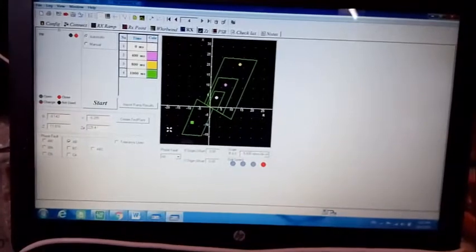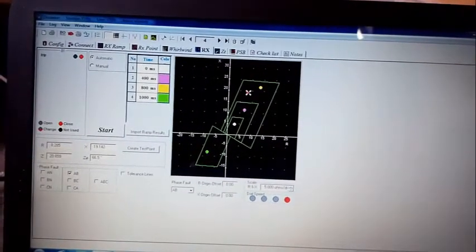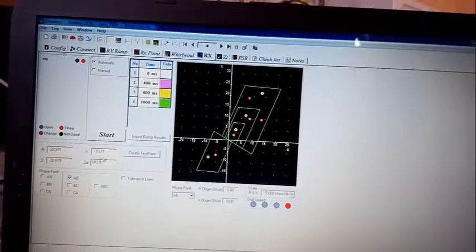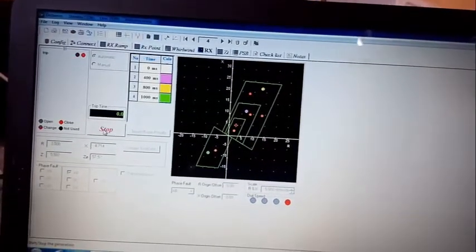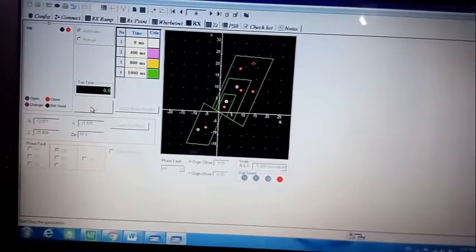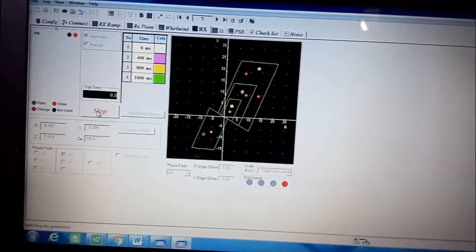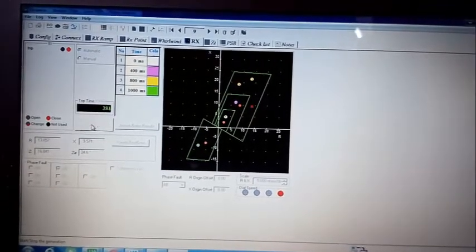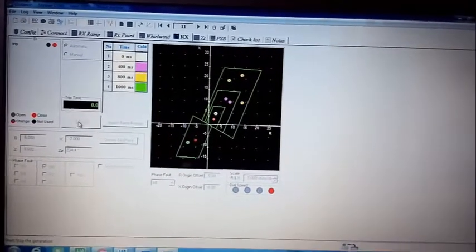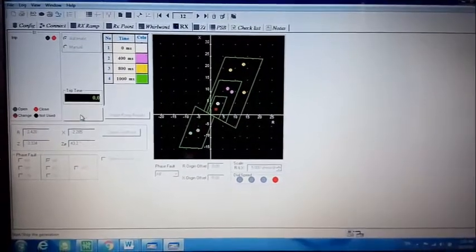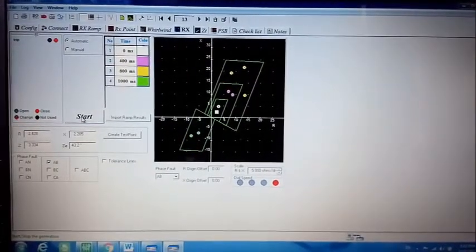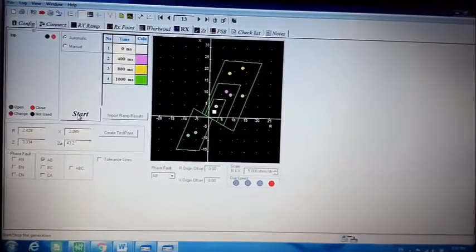This was the timing test. You can create more faults at different points to check how the relay behaves. For the first point, the relay trips in zone one; moving along the line the pattern follows zone two, zone three. After finishing all the test points, FREJA stops automatically. This is how you test the timing of the distance relay.